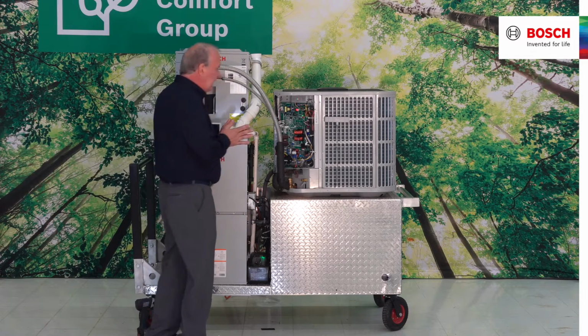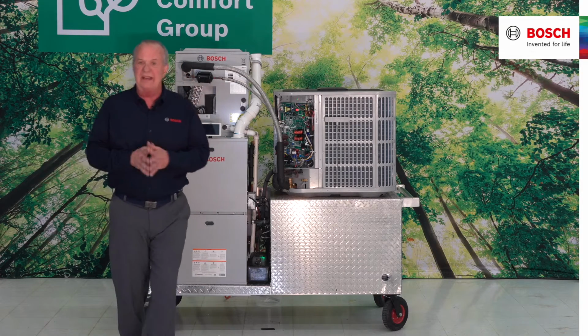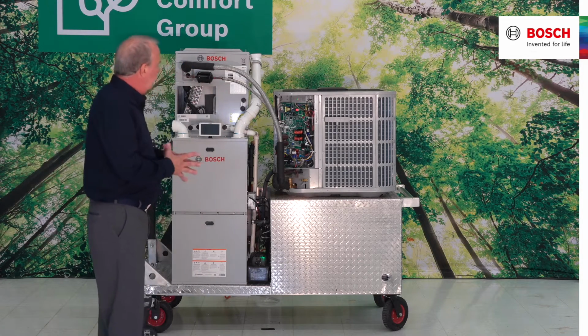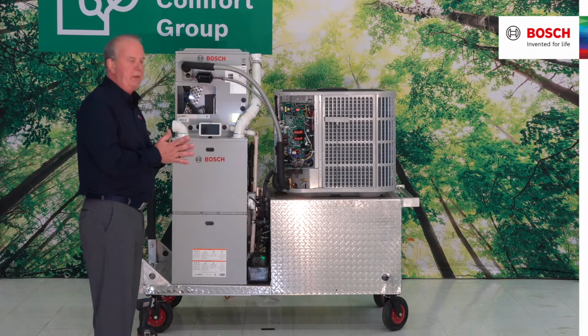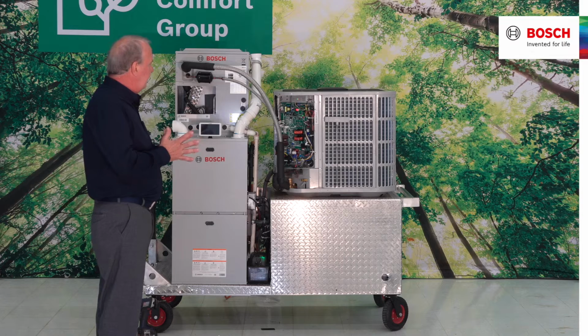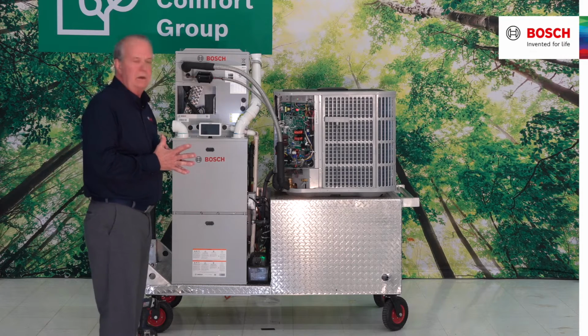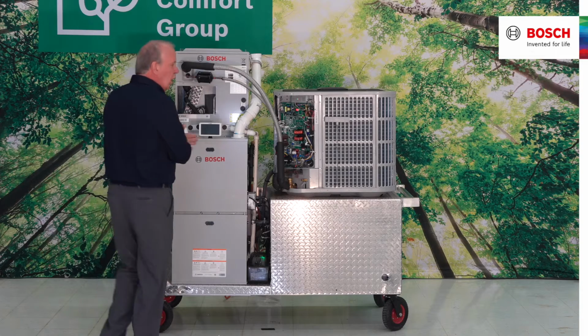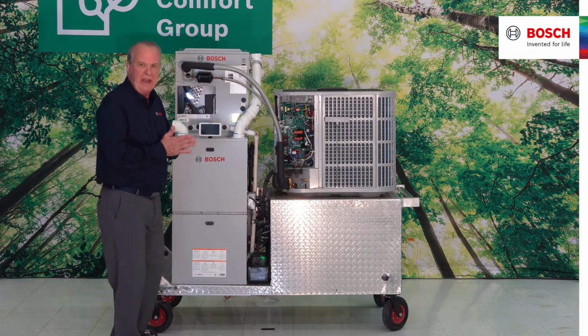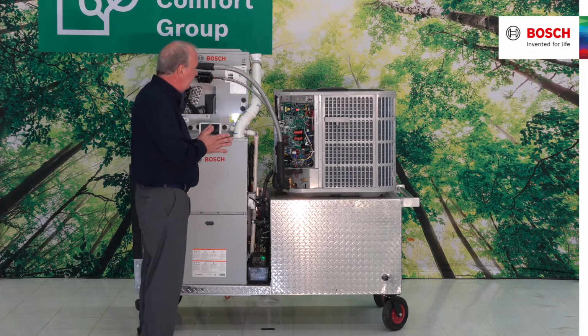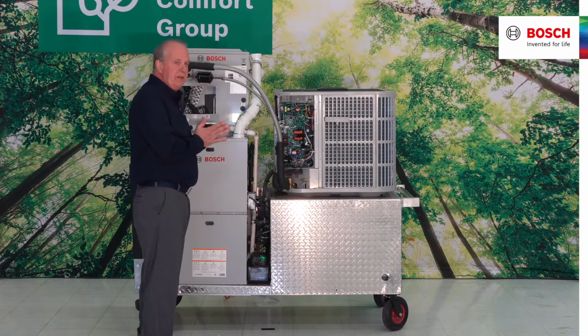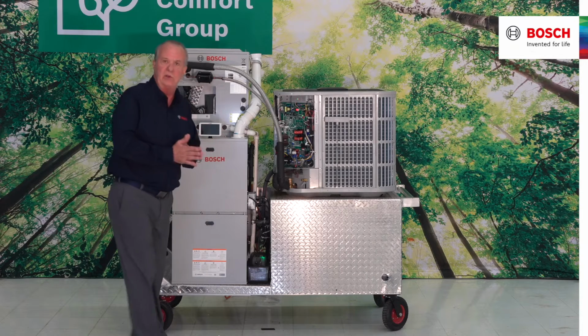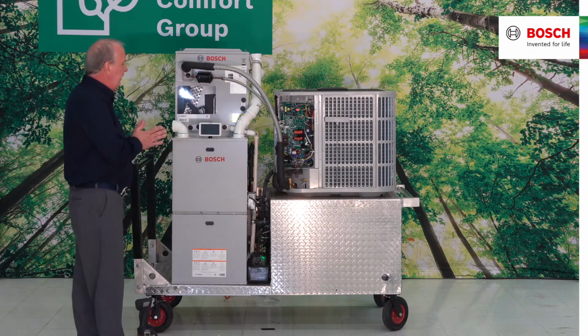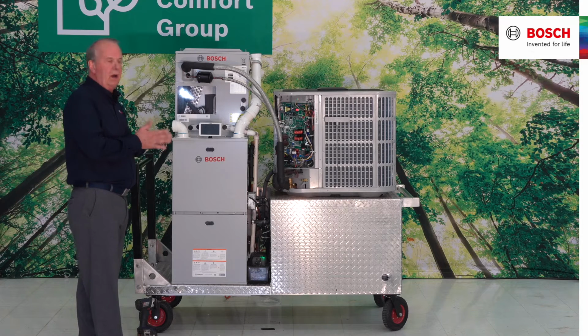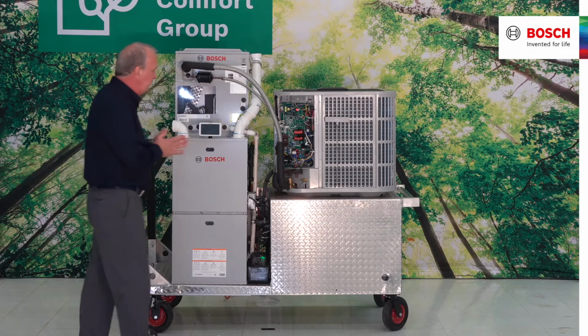And there are calculations that need to be done when you exceed that 15 feet. In your installation manual, your IOM, in the service manual, so on and so forth, you will see that you're going to add 0.6 of an ounce for every foot over the 15-foot factory charge that comes included in the equipment. Now, that is the preferred method. The preferred method is to weigh in the refrigerant. That gives no room for error. That makes the charge exactly where it needs to be.